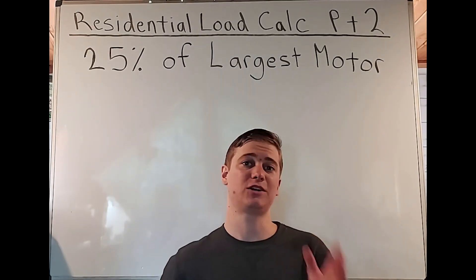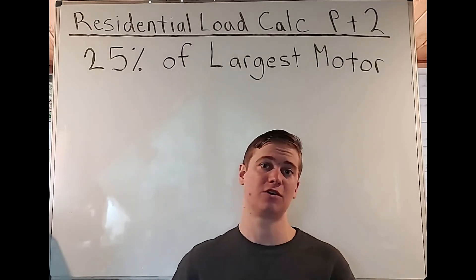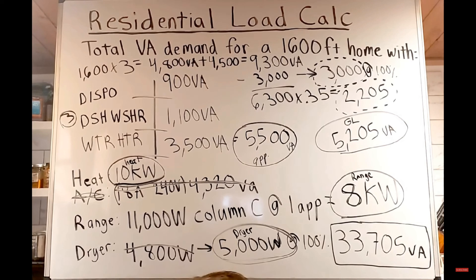So it's going to get the whole shebang and it says the additional 25% of the largest motor. So I'm going to take an actual example from my last video called Residential Load Calculation. As you can see here, I'm showing a screenshot of the final answer. With this, you can see we ended up with 33,705 volt amps there in the bottom right corner.